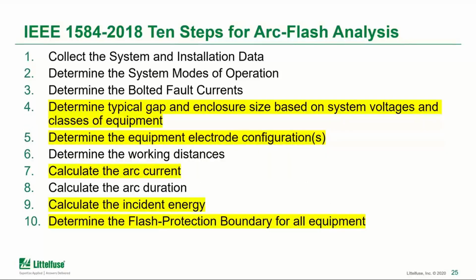I go through those last points really quick because I want to highlight those more on this slide. So here, the 2018 version adds one more step. So it goes from 9-step to 10-step. And what I've highlighted in yellow is really what has changed. So the bolted fault currents, that's a short circuit current analysis, that might be done to IEEE 551 or another standard. The gap size, the gap and enclosure size listed there as step number 4. There are default values that are given in the standard for that. Step number 5, the electrode configuration. So we went through those different configurations. That is important to make sure that the calculation will come out with the correct value. So that's something new to select.